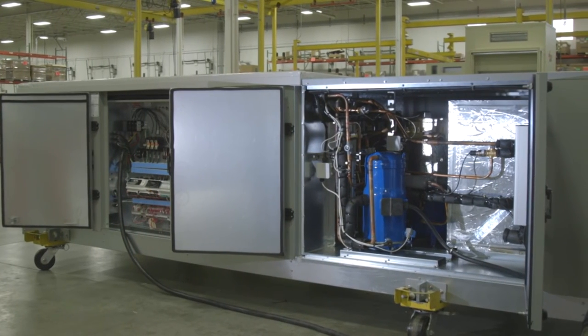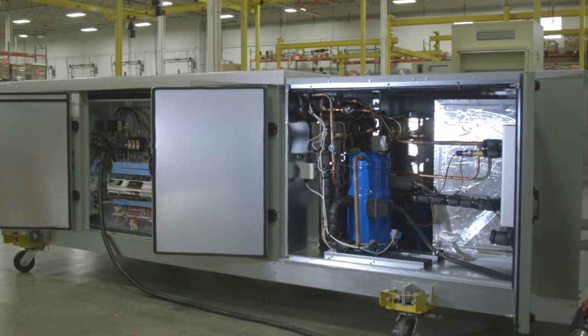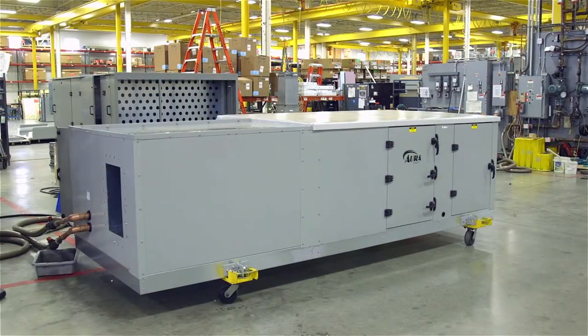The Danfoss Inverter Compressor is at the heart of a unique refrigeration layout that provides heating and cooling of outdoor air. The Desert Air design is unique in that it is a non-reverse cycle heat pump. With only three heat exchangers, modulating valves, and variable speed inverter compressors, the system provides precise leaving air humidity and dew point. The non-reverse cycle optimizes heat exchanger effectiveness. This precise control and refrigeration system cycle enhancements create the highest DX-DOAS efficiency in the industry.